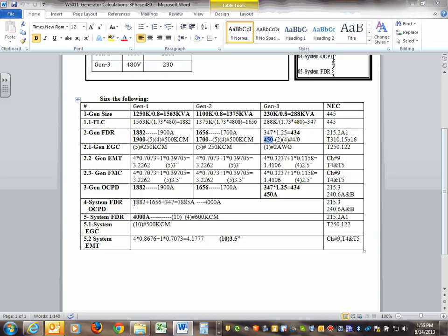What I usually do personally is I add the full load amp of all of them. This is what I came up with. My next adjustable circuit breaker, I put 4000 amp. I could have probably gone to 3900 amp, but you need a frame of 4000 anyway. So I size my system for 4000 amp directly based on the full load amp of these equipments. At that level, guys, you don't have to multiply by 1.25. So I got a 4,000 amp.